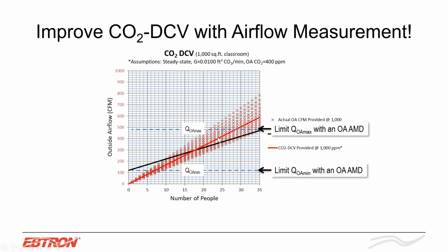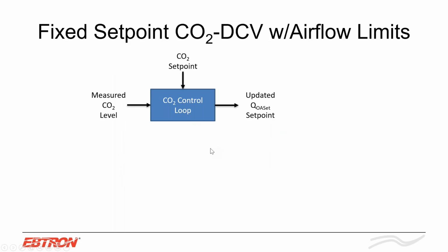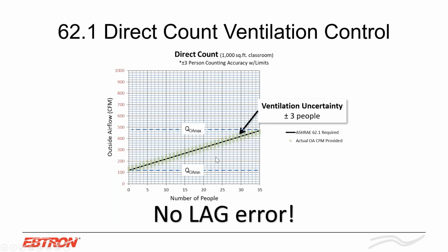The CO2 readings right here, we have more uncertainty. So think about doing population. The other thing that I didn't even hit on yet is lag error associated with CO2 sensors. All CO2 sensors really have an inherent lag. It's about 20 minutes. So, if you have a big gymnasium and you have a CO2 sensor on the wall, first off, it's dependent on where it's placed. Secondly, it's dependent on where the people are.